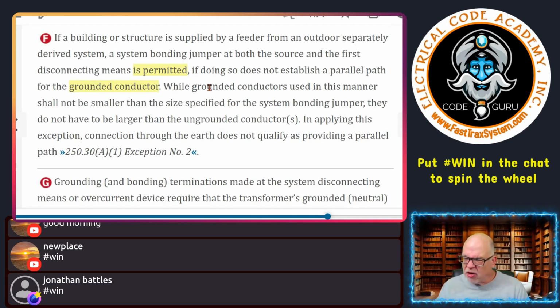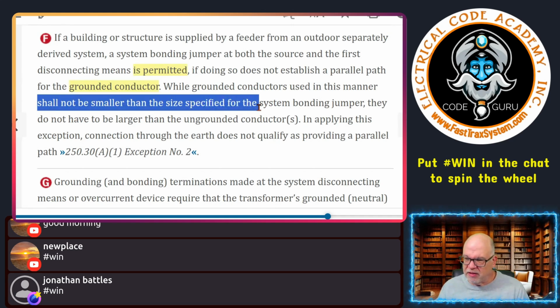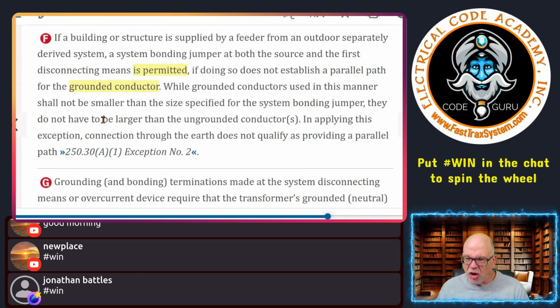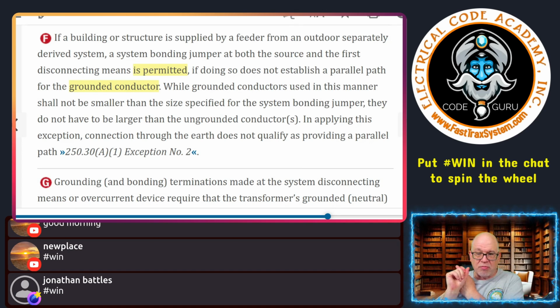Okay. Now, grounded conductors used in this manner shall not be smaller than the size specified for the system bonding jumper. So a minimum sizing requirement. It says they do not have to be larger than the ungrounded conductors. So those conductors that are coming from the outside transformer to the inside location, say a panelboard inside, then again, it's got to be at least sized what? It's got to at least be sized for the grounded conductor, not smaller than that, but can't be smaller than the system bonding jumper. But this conductor does not need to be larger than the largest ungrounded conductor that's in that raceway.